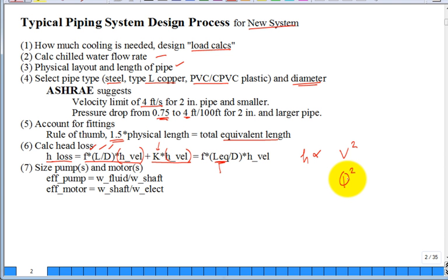And we saw that in the Hazen-Williams correlation or equation. And then size your pumps and motors. Be careful. The work that goes into the fluid, you put a shaft work into a device called a pump, but not 100% of it gets into the fluid. Often you calculate what needs to get into the fluid. Hence, I size the motor to drive the pump based on the efficiency of the pump. And so shaft power and the fluid power, that's the efficiency of the pump.